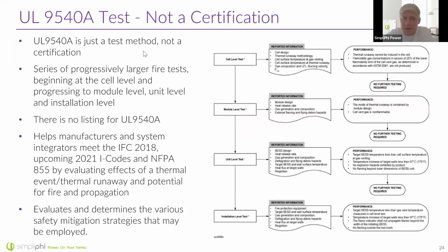9540A is a test method. It's not necessarily a certification such as a pass or fail. 9540A is basically a test that's performed and a report that is in turn generated by a third party. That third party for us was UL, which is Underwriters Laboratories. We provided them with multiple BOSS cabinets full of real batteries, and those batteries were basically drilled into and thermocouples were installed. The batteries were heated with a forced external heat, so they wrapped cells with heaters, trying to force a fire on the system and measuring the temperature all around.